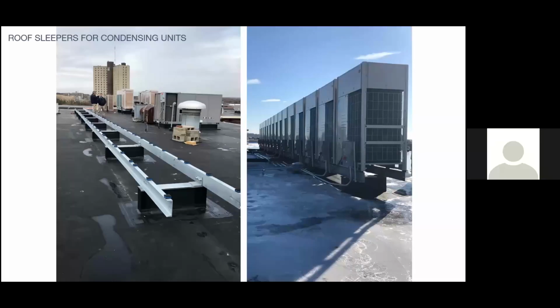There are also non-penetrative versions of this, which need to be pre-engineered to withstand a specific wind rating. We've run into a few different projects where we went with these, as you couldn't fix the alternative stands into the roof. You just need to make sure those are always designed properly in advance and correctly specified as well. The other alternative, and what we went with here, are condenser unit rails, which make for a pretty clean install, especially with long rows of condenser units like you can see here on the right. These can still be used even if you have just 1 or 2 units as well, which we've also done in the past. As you can see, it looks pretty clean and simple.